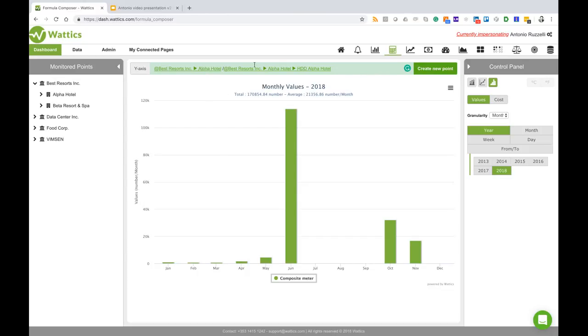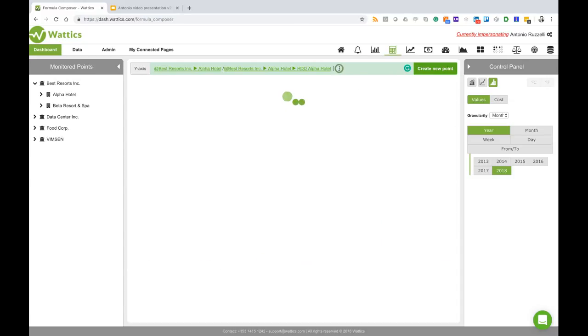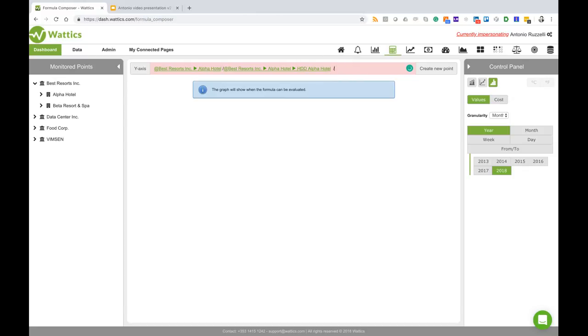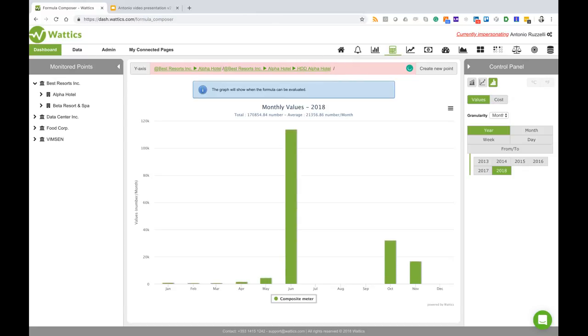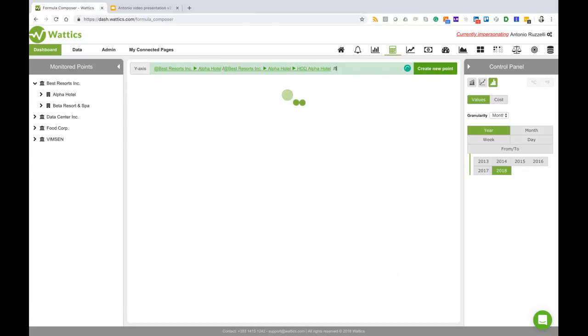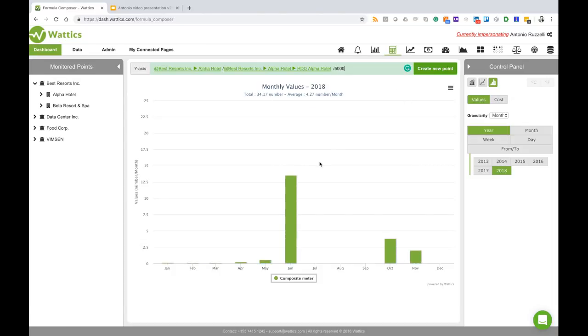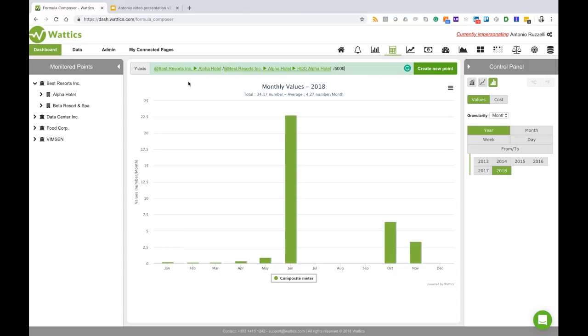Now if I want to be even more specific I can divide this by the size of the hotel. I know that Alpha Hotel is 5000 square meters, so I can divide by 5000 and that will create the kilowatt hour per heating degree days per square meter for Alpha Hotel.